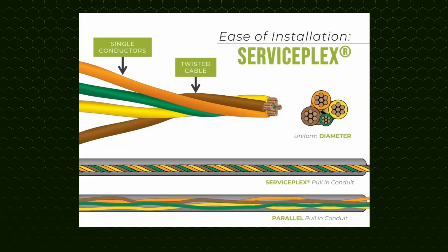Contractors who use ServicePlex report 50 to 70% combined material and labor savings. Plus, ServiceWire will cover the twist loss on our end, so you don't have to modify your order for this value-added service. ServicePlex is easily installed in conduit, concrete, or directly buried, just like our single conductors, and it is available in all industry standard colors, 14 gauge to 750 MCM and XHHW2, USE2, or RHW2. ServiceWire offers shorter than industry lead times for Plex in colors or black, and we can even cut ServicePlex length by specific pulls or install pulling heads upon request. There are tons of options for this unique product.